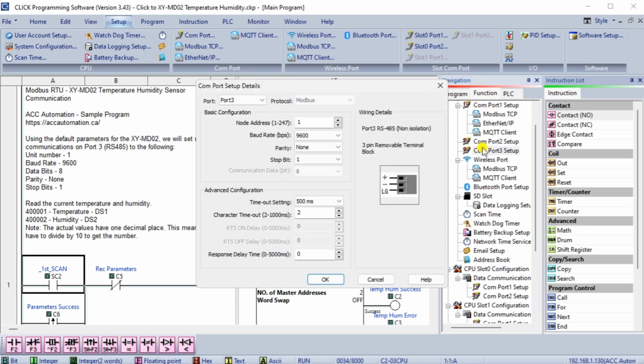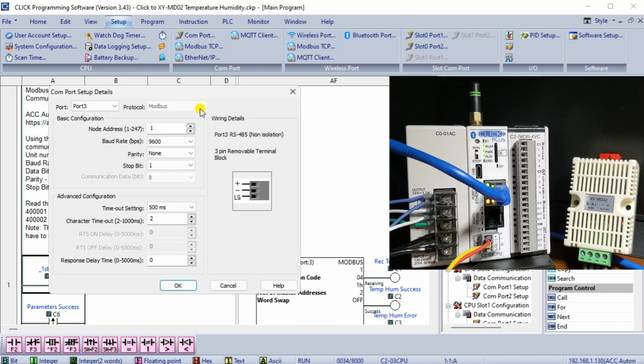The COM port setup details window will now be displayed. The port showing is 3 and the protocol is set for Modbus. To the right hand side you will see the wiring details with a picture of the port. The basic configuration will be the communication that the network will use. Since this is the master or client, we'll leave the default node address as 1. The baud rate will be 9600, parity none, 1 stop bit, and 8 data bits. This is the default for the XY-MD02 temperature and humidity sensor. We will leave the advanced configuration as default. Our RS485 port is now set for the sensor.